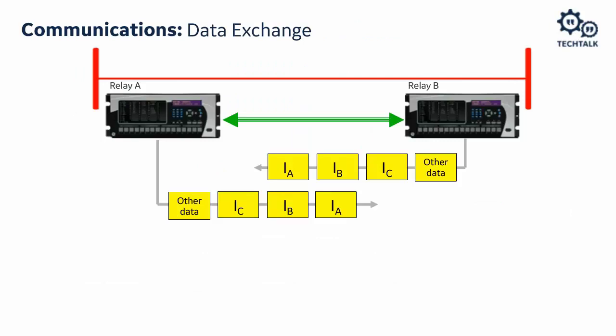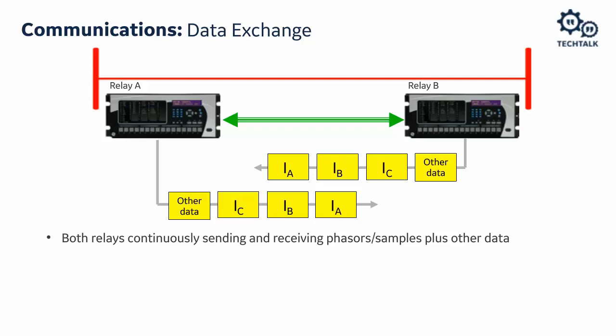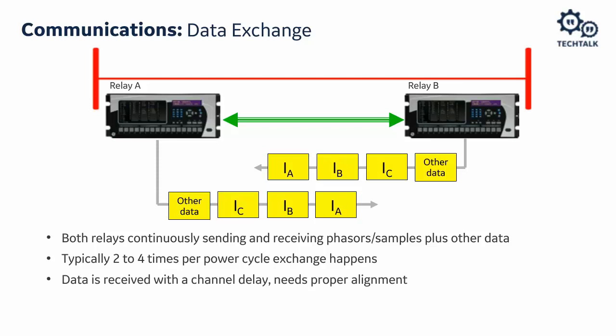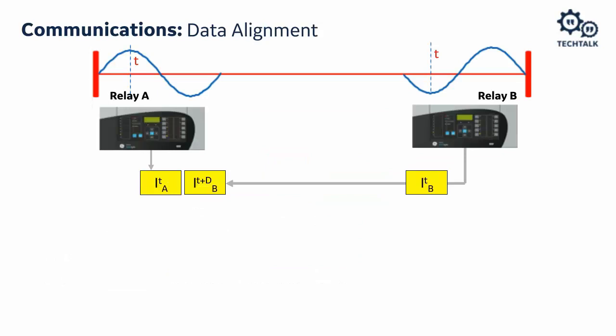What are we sending in the communication package? We send current phasors plus other data: direct transfer trip, control data to let the other relay know it is not blocked or experiencing errors, direct I/Os (eight bits) for control purposes, and other data. Relays exchange phasors or samples plus other data continuously, typically two to four times per power cycle. However data comes with channel delay and needs proper alignment.